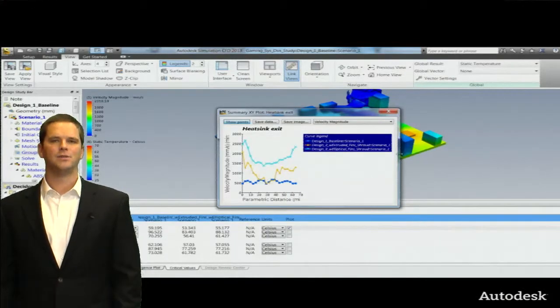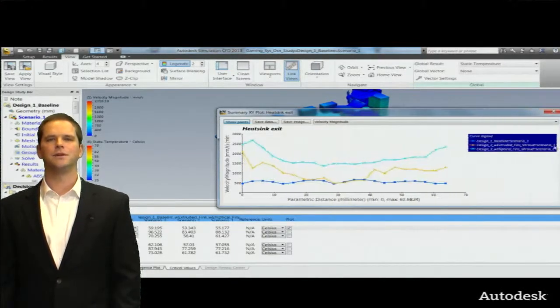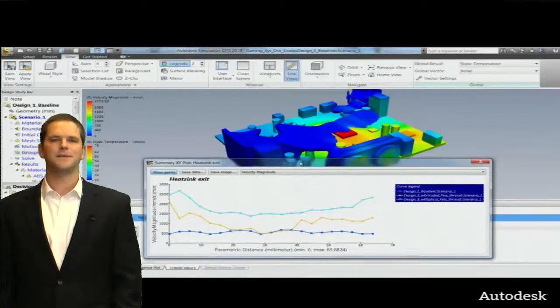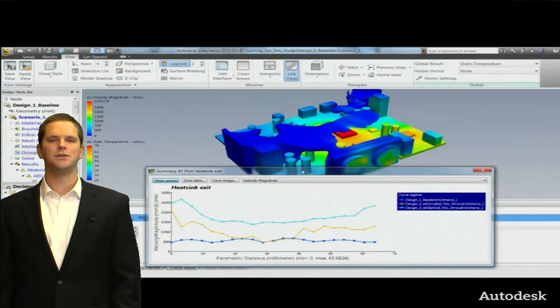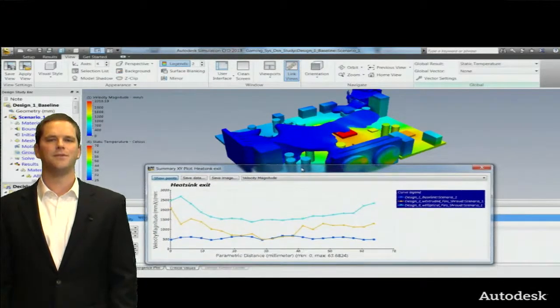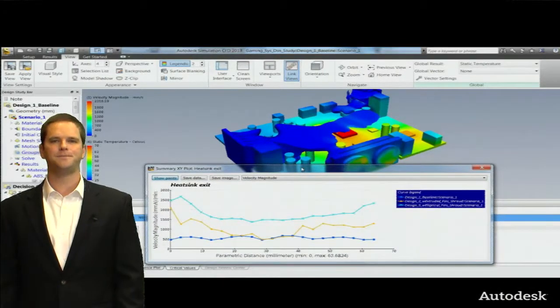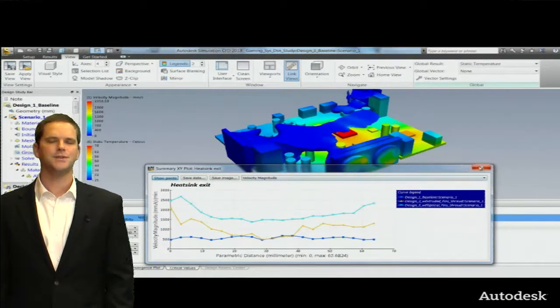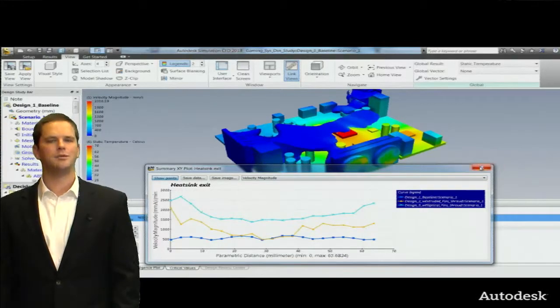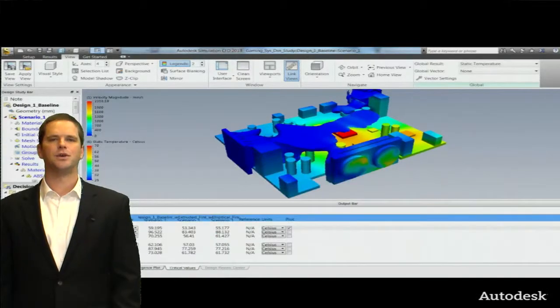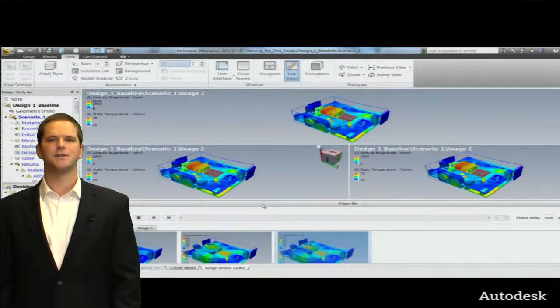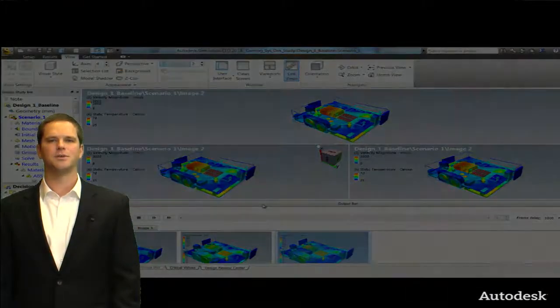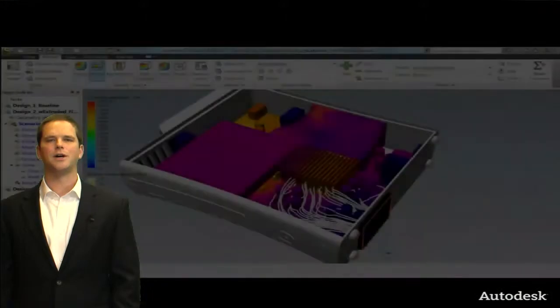And then one of the last things we'll do here is look at the actual velocity at the outlet of the heat sink. Again, we've continued to drive that up using the shrouding. And so we've been successful on all fronts in making some changes to drive down those temperatures and drive up reliability.